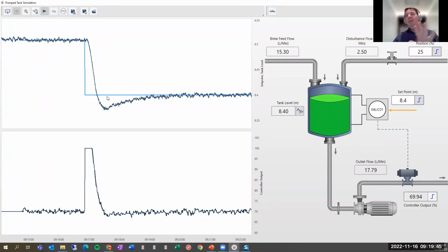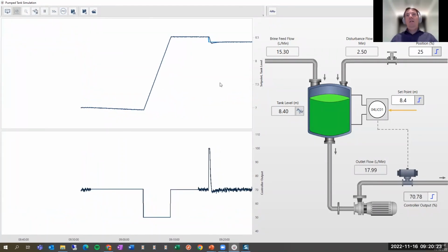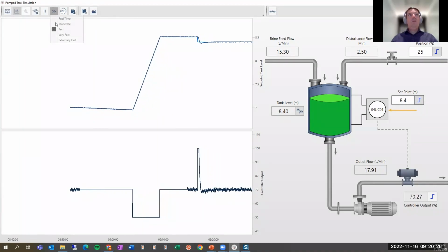Okay. So this is the tuning we came up with, an aggressive gain and an integral of 1 minute. The first thing you may notice is we don't have the same response as we had with the self-regulating. So even though I'm using aggressive gain, I'm not getting the overshoot, undershoot, the small oscillation of a strong aggressive gain. But I do get an overshoot on my process. Before with self-regulating, the reflex would say, well, if I'm overshooting, it means I have too much gain. But this is not the case.